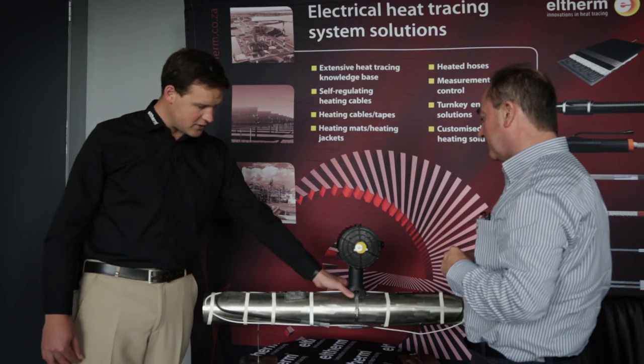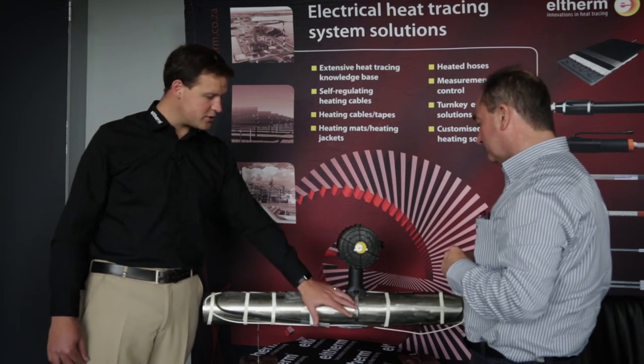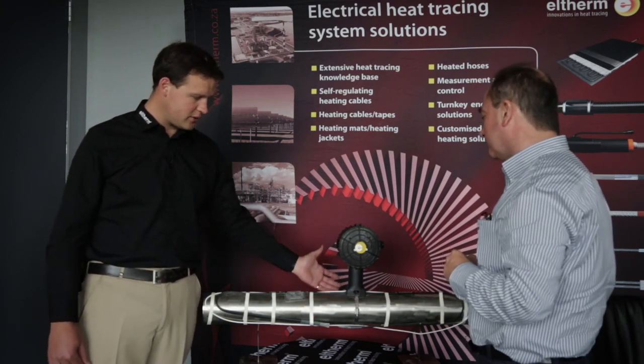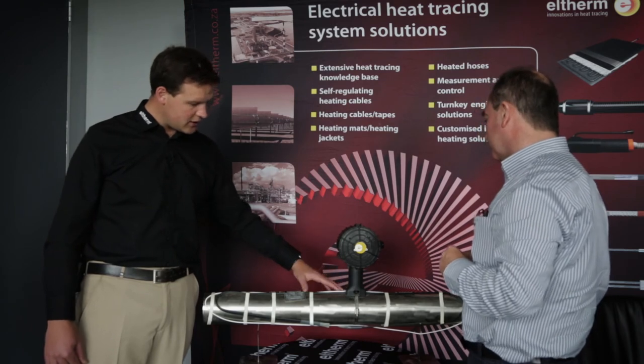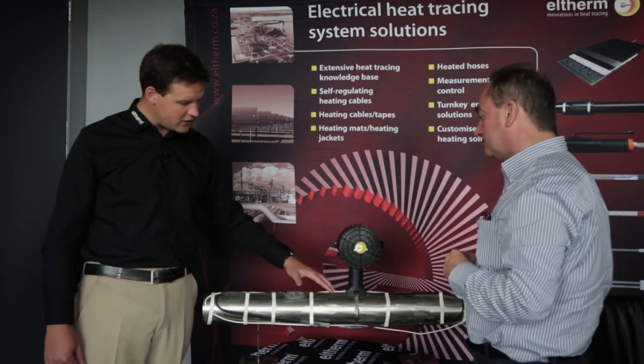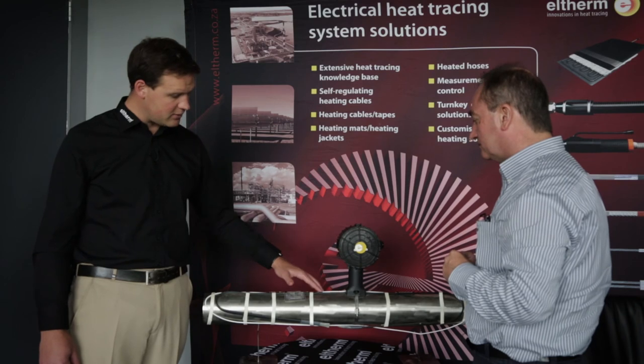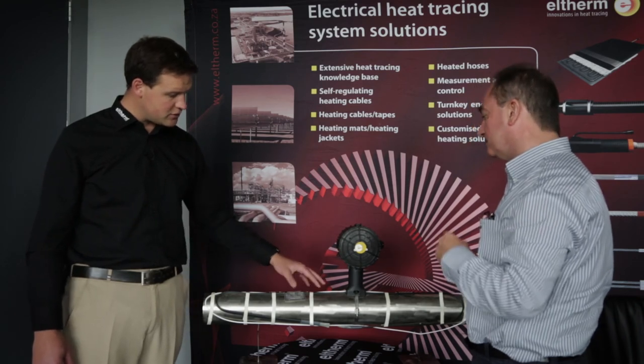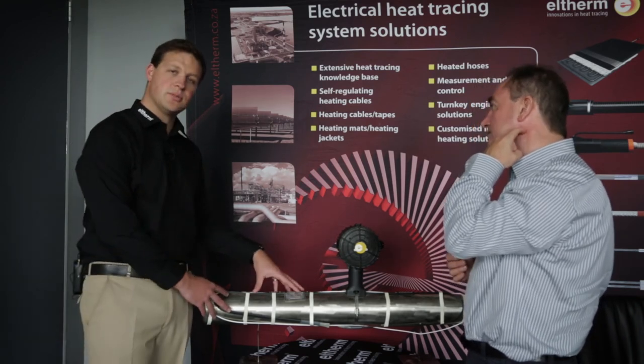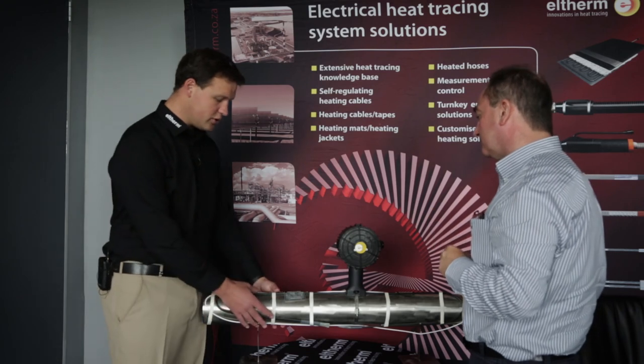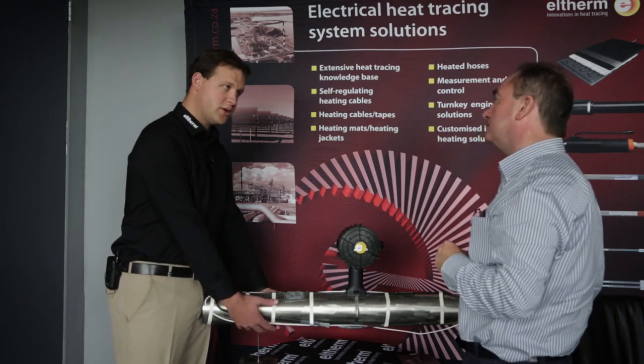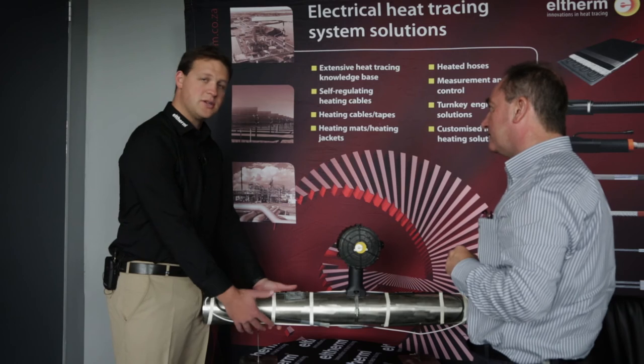It's literally fixed to the pipe using a screw-mounted clamp, nothing too fancy there. As you can see, what we then do is we heat trace - you place the cable on the pipe. Traditionally, this is just for demonstration purposes, but traditionally what you'll do is place your cable on the underside of the pipe, as heat rises.